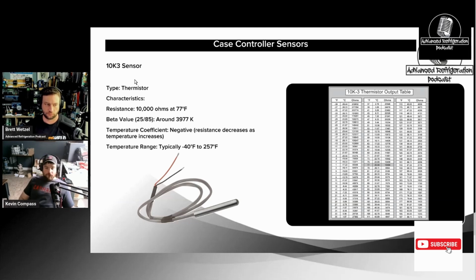So what you're going to want to do is disconnect it from the board. You're going to want to take your meter and put it on ohms, and check across signal and ground of the sensor. So you have the two wires you want to check. You're going to want to compare your ohms to what the chart is. Don't have your hands on the wires. I usually leave it in the plug and then pull it off the board and then check it.